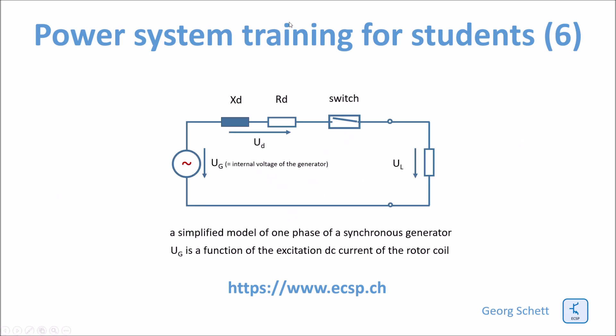Here we have a very strongly simplified model of the generator. It's one phase of the generator — we can do that because we assume the generator is symmetric, so there is a symmetric load. Here we have the voltage source, which is proportional to the internal voltage of the generator. The internal voltage of the generator is a function of the excitation DC current of the rotor coil.